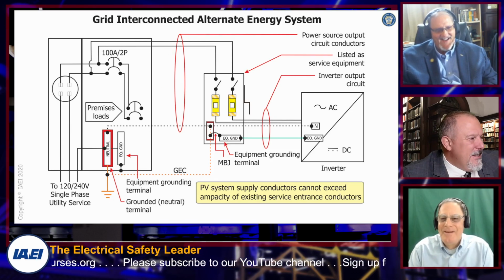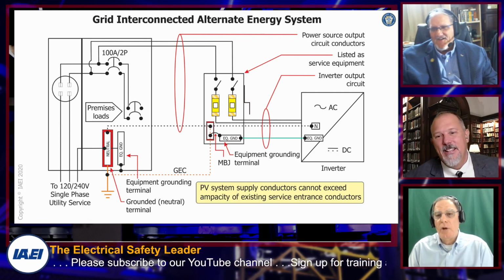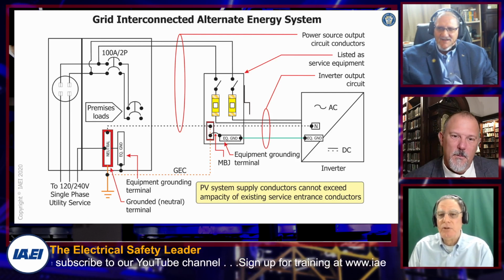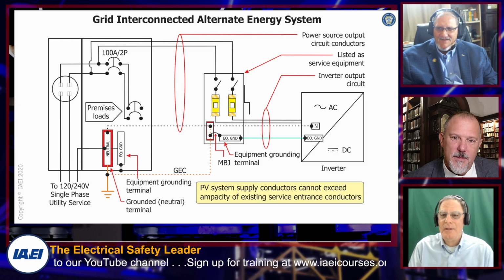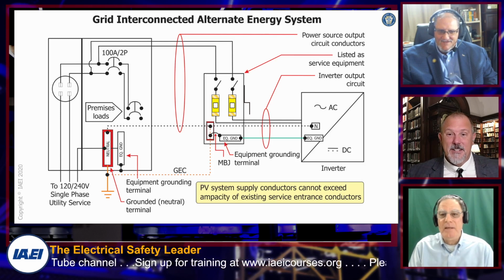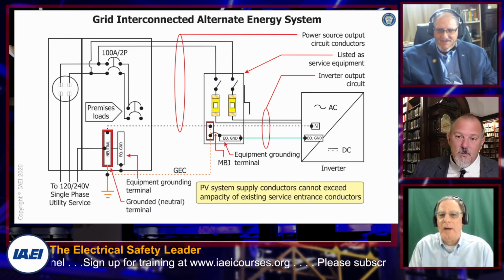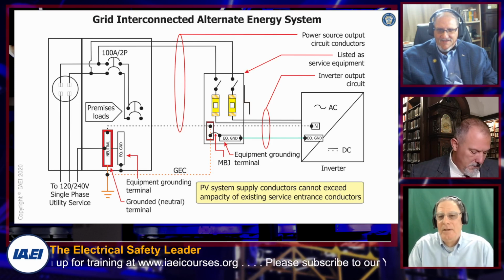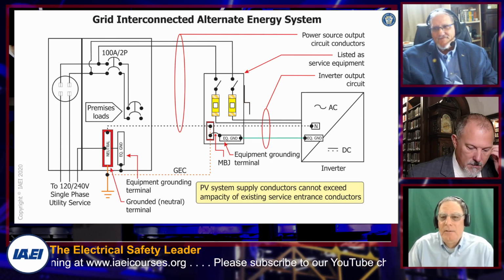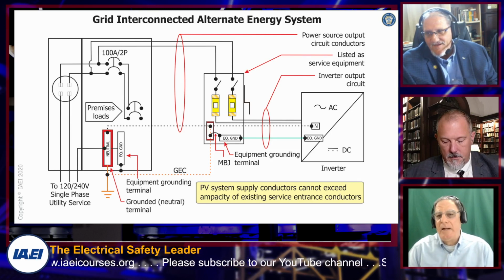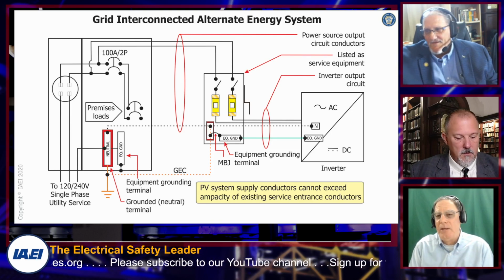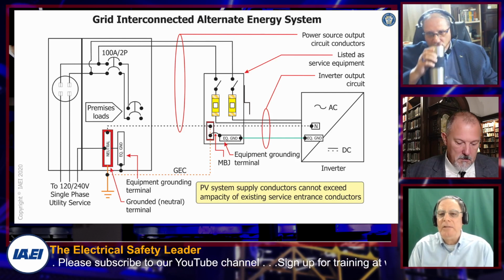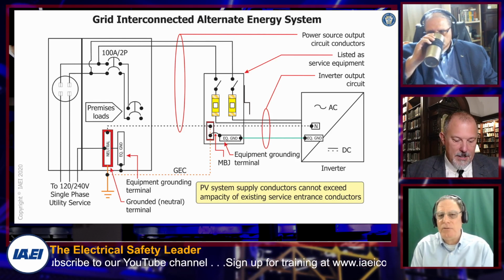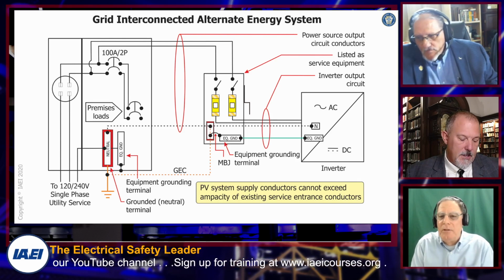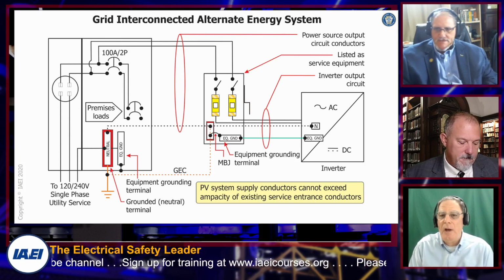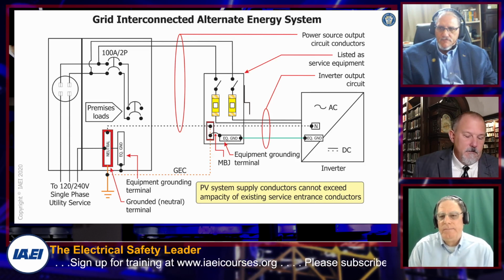Yeah. And again, we talk about definitions. This definition of service changed in the 2020 code. It was a significant change, but I don't think a lot of people realize how significant it is. But when you look at it electrically, you can call those wires anything you want. They're going to operate the same way. I call it a service entrance conductor, a power source output conductor, it's going to operate the same way in a current flow, fault current situation.